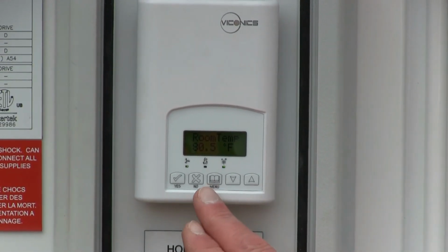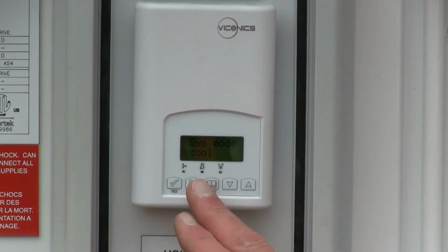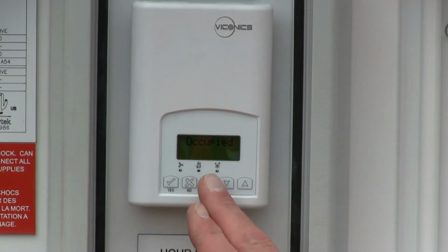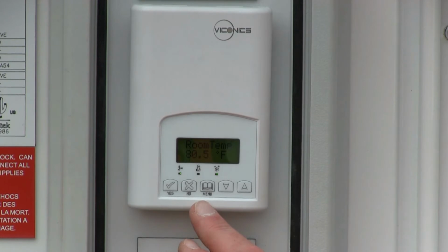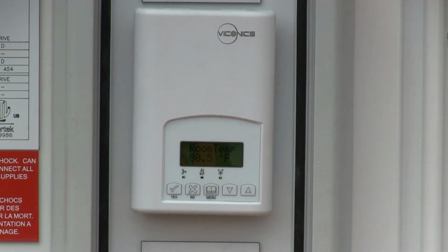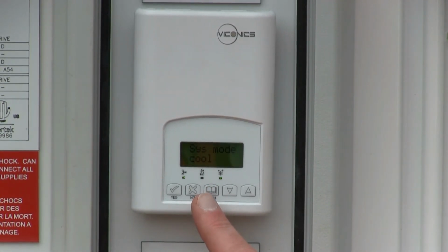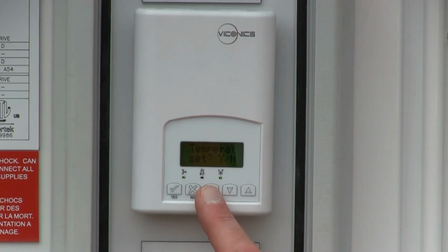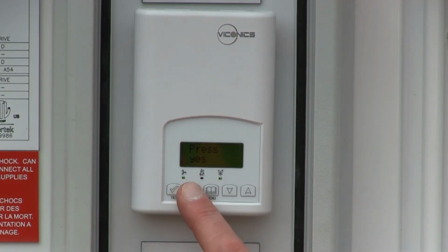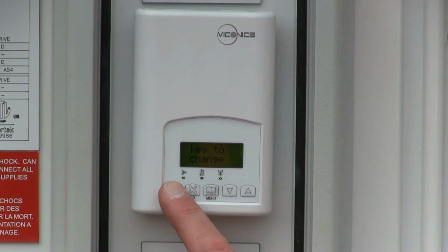And you'll look at the rolling display right now. It tells you the system mode is in cool. It's currently occupied, and the current room temperature is 80.5. So to go in and change the mode, you're simply going to push the menu. It's going to say temperature set yes or no. We're going to say no for now, but now it's going to give us the option to say system mode set yes or no. We're going to say yes.